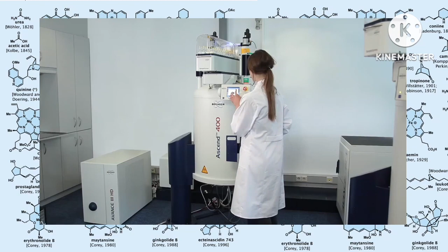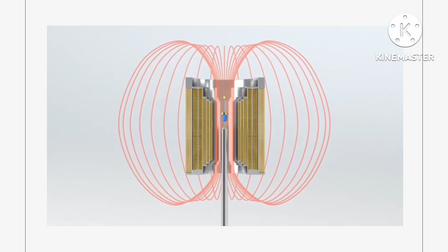Samples are inserted in the center of the magnet and are positioned in the NMR probe, so the sample is located at the position of the strongest field and highest homogeneity of the magnet. The NMR probe consists of coils that are used to excite the sample and record signal responses at radio frequency.